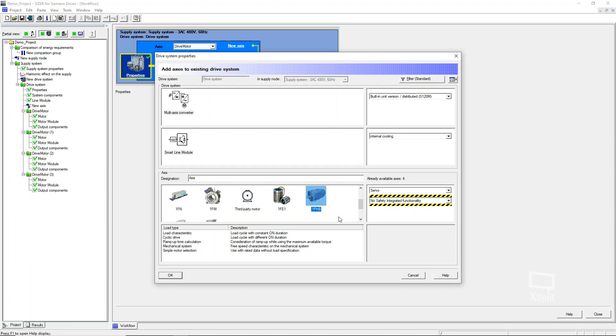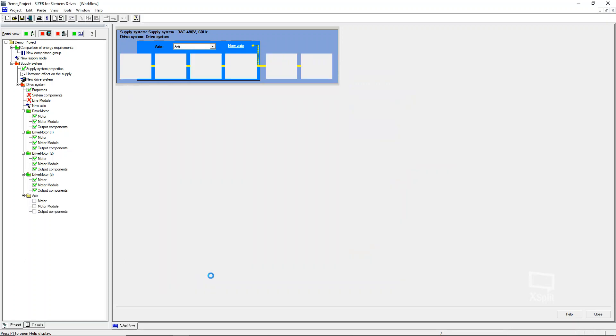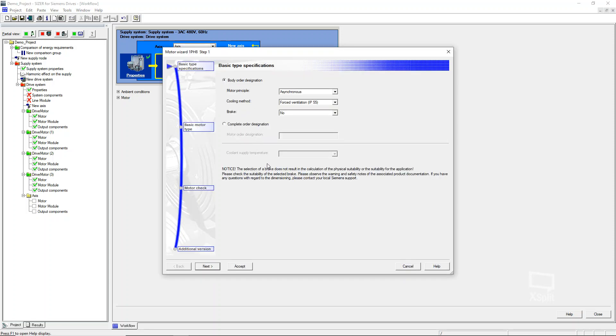I actually have a customer that reached out and was asking just some information about overspeeding a motor and running above rated nameplate. One of the things about these 1PH8 motors is that they have a pretty high mechanical maximum speed. They are rated down around that 2000 RPM most of the time, but they actually can go, some of them can go up to 10 or 12,000 RPM. Sizer actually gives you all of the motor curves and the torque characteristics of these motors built into the tool. Just create a new axis, select the type of motor that you want, and then do a simple motor selection.